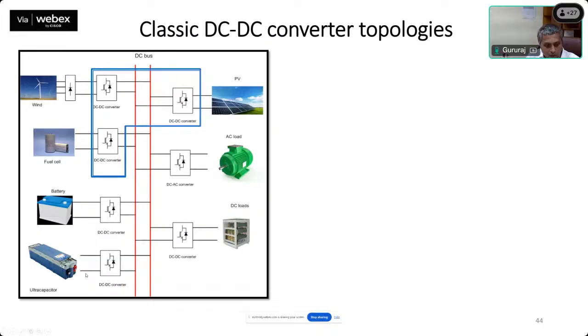What is the role of the ultra capacitor? It's a high power density device, unlike the battery which is a high energy density device. This ultra capacitor absorbs the transients - the switchings that come up because of changing irradiation, power output reflected as sudden change on the DC bus, or sudden switching of loads due to dynamics on the DC bus.